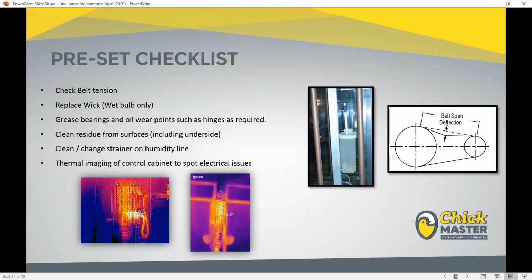Now, we do have a guide, which is in the rear of all of our VIDA manuals, detailing the correct belt tension. In an ideal world, what you do is get yourself a belt tensioning tool. This is a spring-mounted clip, which you push onto the belt until you get about 2 inches of deflection. You then take note of the amount of force it took to deflect the belt, and that is the measurement of a correct belt tension. And the belt tension should be taken when the fan is not running, correct, Craig? Absolutely correct, yeah. At no point when you're inside the machine should the fan be running. It's basic health and safety. Okay, very good.